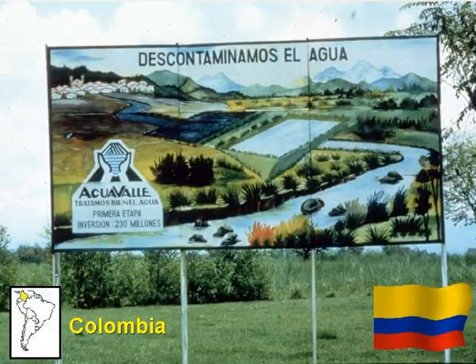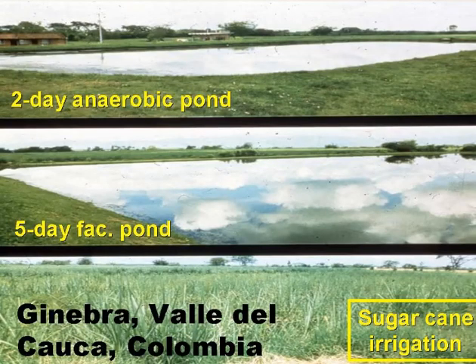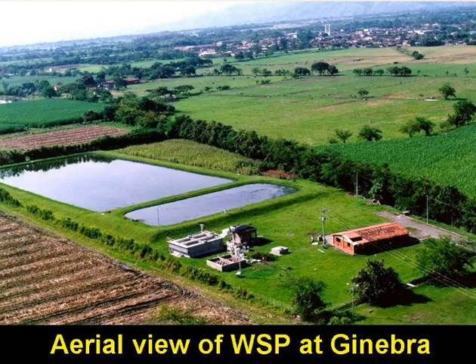This is Colombia in South America. Very little wastewater — only about 10% of the total — is treated in South America, although in some areas it's better than this. The slide shows a poster by Acuavalle, the water and sewerage company in the province of Valle in the south-west of the country. The poster says: 'We treat our wastewater.' This is one of Acuavalle's pond systems, serving the small town of Ginebra. The wastewater flow is about 25 litres per second, and it's treated in a two-day anaerobic pond and then in a five-day facultative pond. The facultative pond effluent is used to irrigate sugarcane, which is the main crop in this part of Colombia. In front of the anaerobic pond are some experimental reactors operated by researchers from Univalle, the main university in the nearby city of Cali.